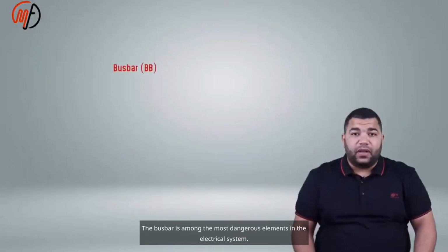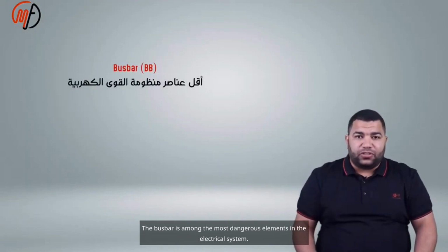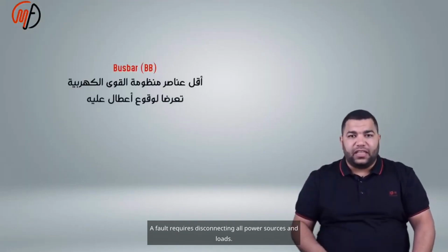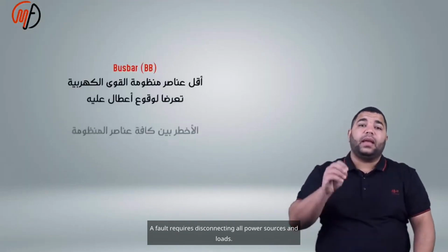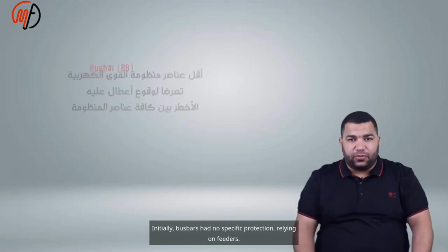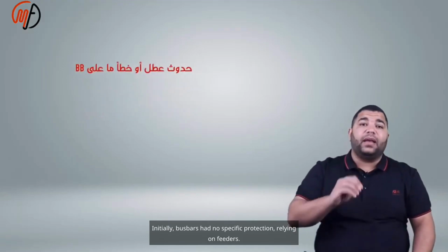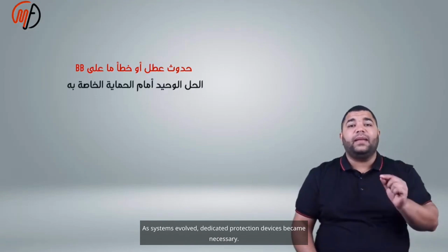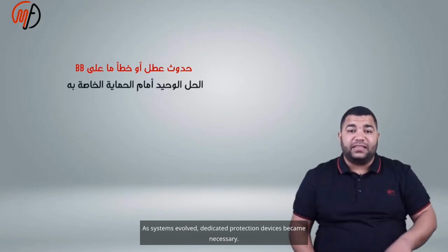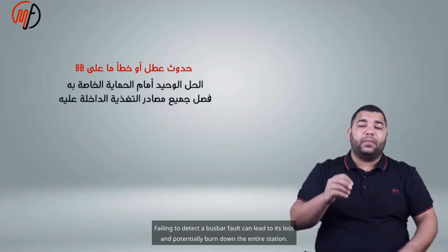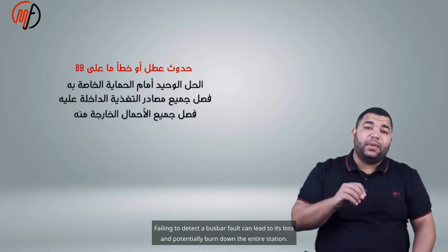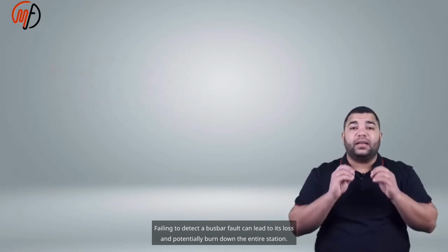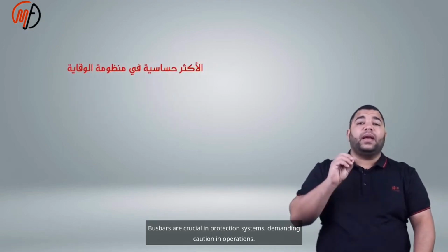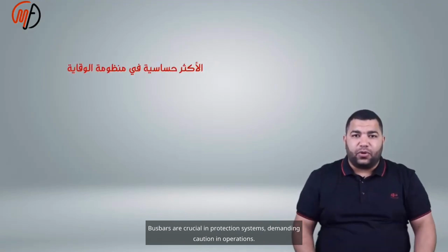The bus bar is among the most dangerous elements in the electrical system. A fault requires disconnecting all power sources and loads. Initially, bus bars had no specific protection, relying on feeders. As systems evolved, dedicated protection devices became necessary. Failing to detect a bus bar fault can lead to its loss and potentially burn down the entire station. Bus bars are crucial in protection systems, demanding caution in operations.